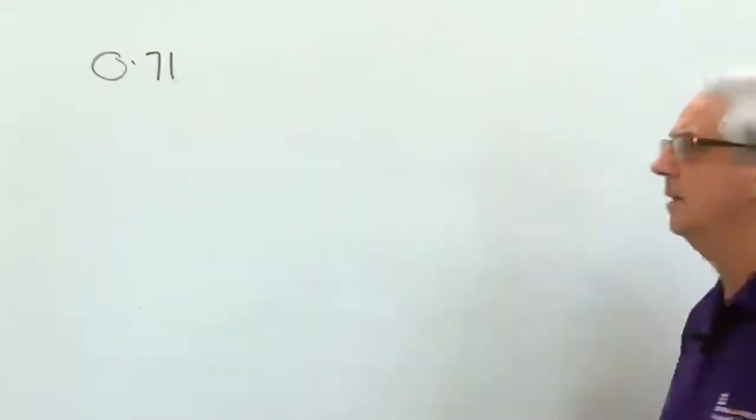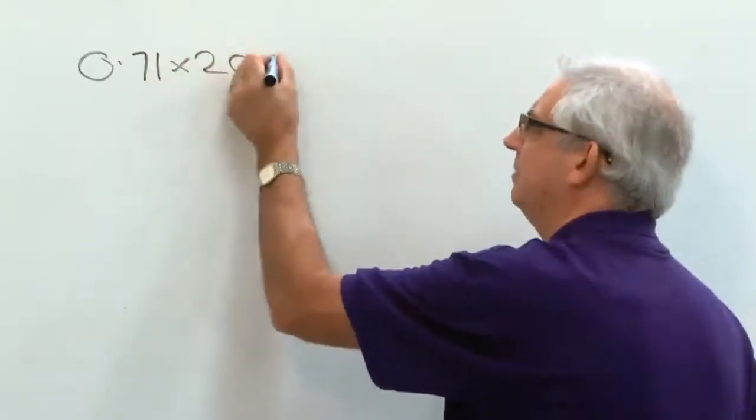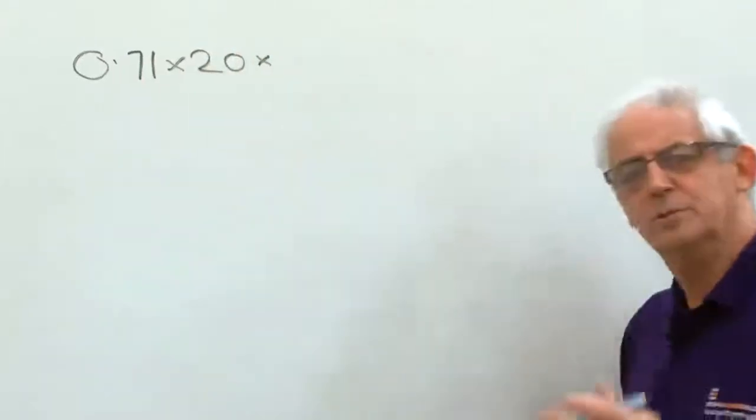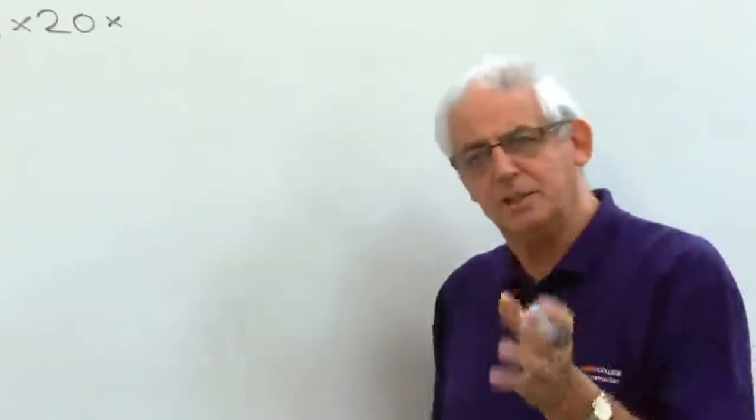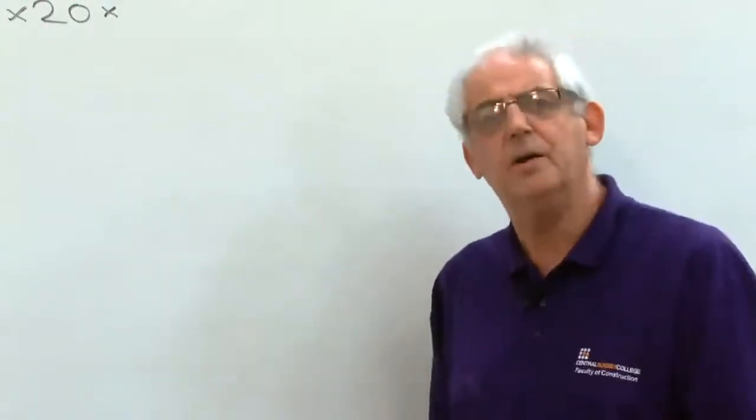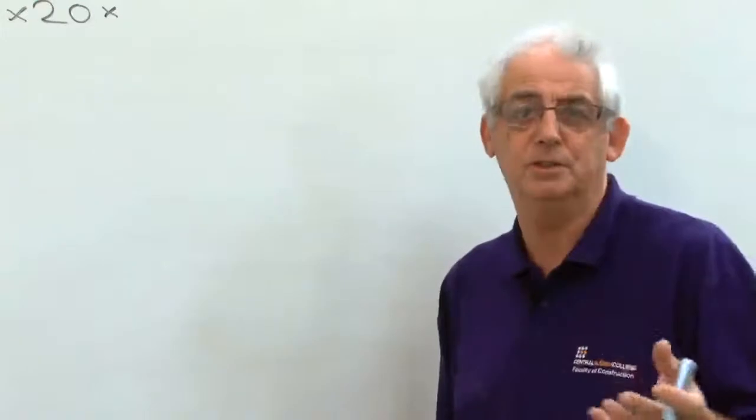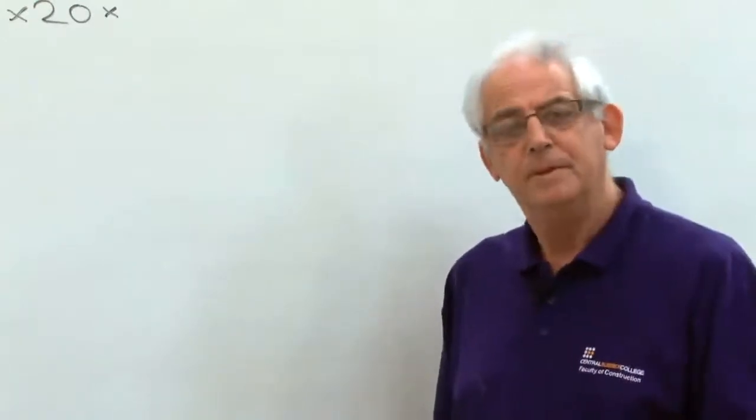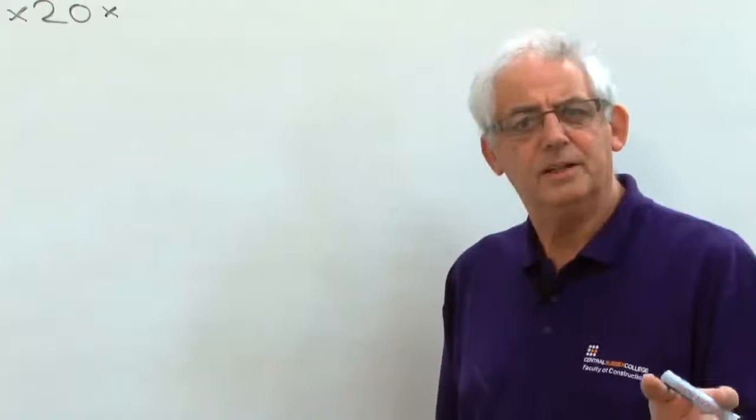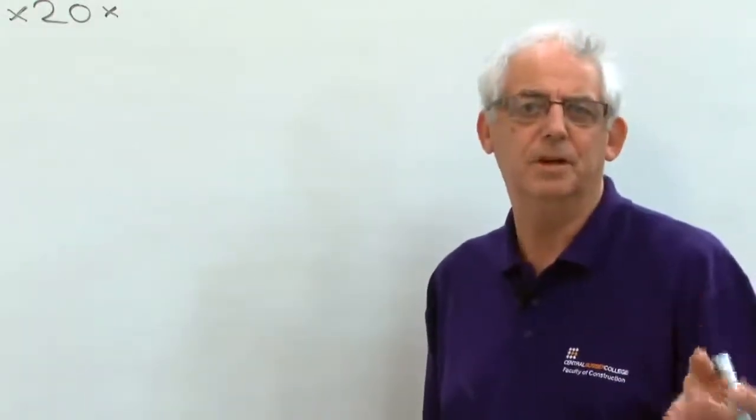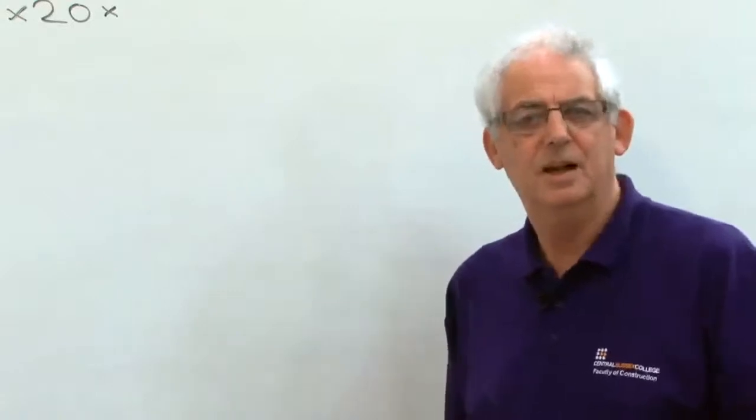R1 and R2 is 0.71. The maximum current that could flow through this circuit is 20 amps because that's the rating of the protective device. But we also know that the temperature of the conductor is going to rise when we pass a current through it.